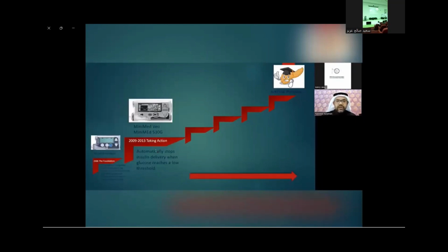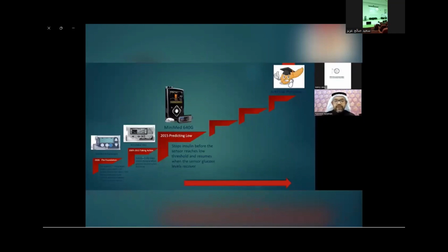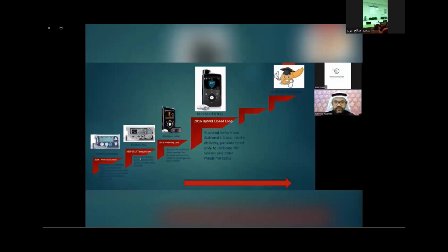Then it got better: the pump and the sensor had the ability to stop the insulin delivery before reaching the low threshold, and that was back in 2015. That's what we call the predicted low glucose suspend, and then it resumes the delivery of insulin by itself when the glucose levels recover. After that, we got the 670 by Medtronic, which not only stopped the delivery of insulin before it reaches the low threshold, but also provided the patients with automatic basal insulin delivery. That means, for example, patients will have different basal insulin delivery at different times of the day based on their sensor value.